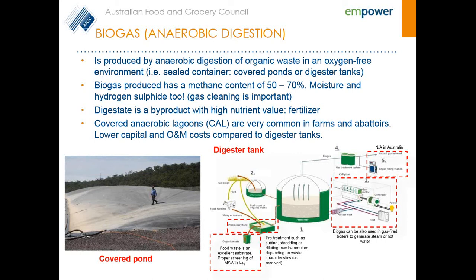There are a number of studies being conducted around this, showing that combining manure or paunch contents from animals with wood waste or crop waste can significantly improve yield. The biogas can be used in a gas engine to generate electricity, fed directly into a gas boiler to generate steam or hot water, or even used in more sophisticated solutions such as grid injection — a more advanced solution we're starting to see in Europe but not yet available in Australia.